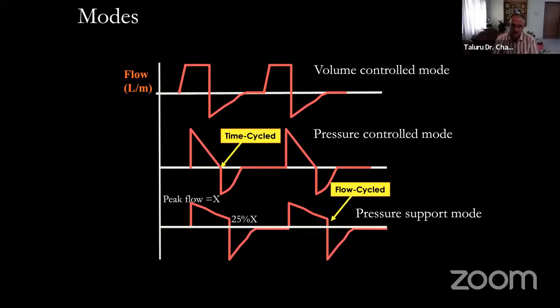If the peak flow is X, at 25% of the X, it cycles. It is adjustable. By default, it is like that. You can bring it down, you can bring it up. Bring it up means at 50% here, 75%, you are shortening the inspiratory time. If you are shortening the inspiratory time, obviously you have to increase the peak flow, which is called the rise time in pressure modes.